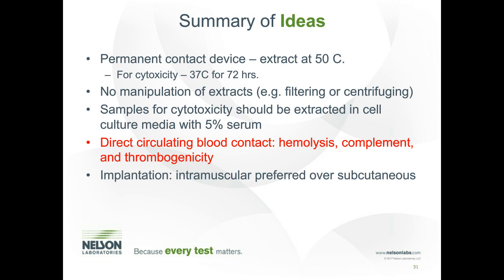But the one thing that the new document does spell out is for cytotoxicity. In the past, we only did 24-hour extractions at 37 degrees because of the L-glutamine in the cell culture media, the impact that heat can have on the breakdown and aggregation of L-glutamine. But now that the FDA has done some internal experiments and evaluations on this, they are recommending that devices that have longer than 24-hour contact with the body do 37 degrees for 72-hour extractions. Okay, this is not the incubation of the media on the cells, but the actual extractions of the medical device. If you have longer than 24 hours, you need to start evaluating those at 37 degrees for 72 hours.